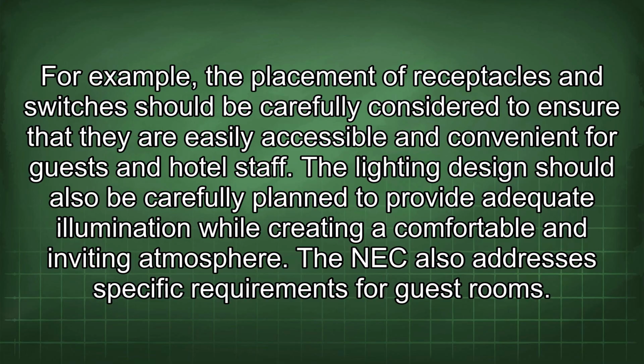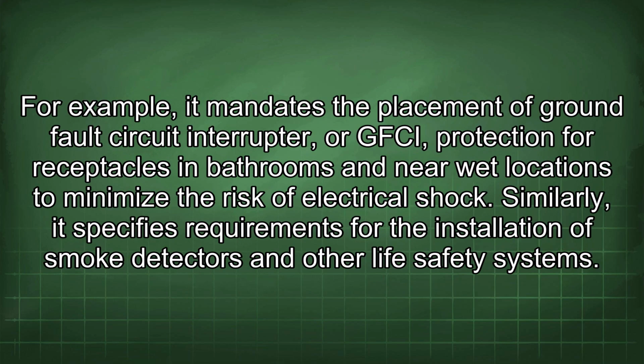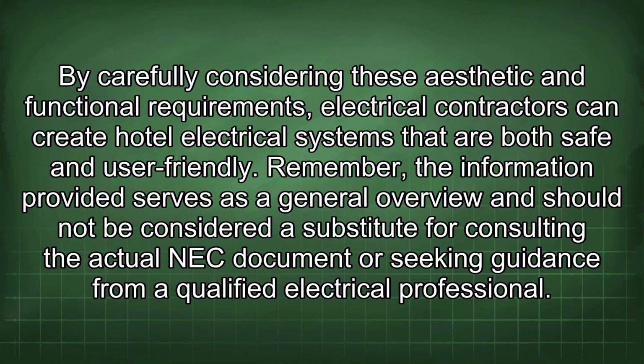The NEC also addresses specific requirements for guest rooms. For example, it mandates the placement of ground fault circuit interrupter, or GFCI, protection for receptacles in bathrooms and near wet locations to minimize the risk of electrical shock. Similarly, it specifies requirements for the installation of smoke detectors and other life safety systems. By carefully considering these aesthetic and functional requirements, electrical contractors can create hotel electrical systems that are both safe and user-friendly. Remember, the information provided serves as a general overview and should not be considered a substitute for consulting the actual NEC document or seeking guidance from a qualified electrical professional.